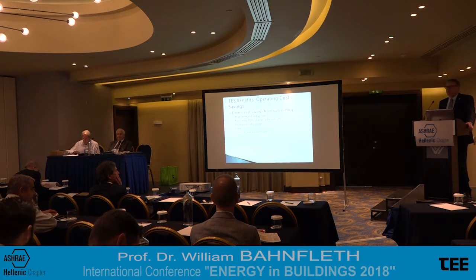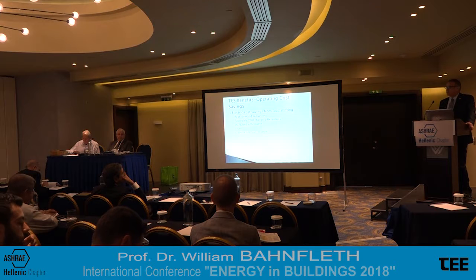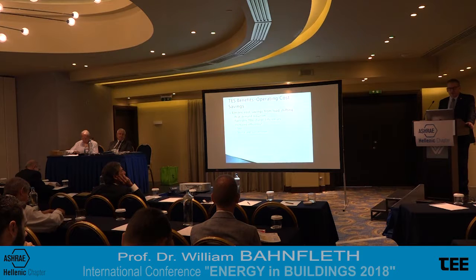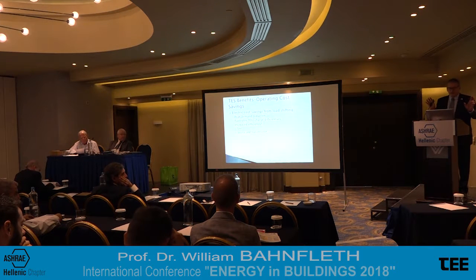The benefits of storage that are normally noted start with electric cost savings. And this was almost entirely the driver for thermal storage if you went back several decades. Users of electricity are charged for the peak capacity that they require, as well as for the total amount of energy that they use. So peak demand reductions lead to savings in demand charges, and shifting of energy use from one time to another to accommodate the operating characteristics of the generating grid will be compensated. You'll be rewarded for that with a differential cost, cheaper at night than during the middle of the day.